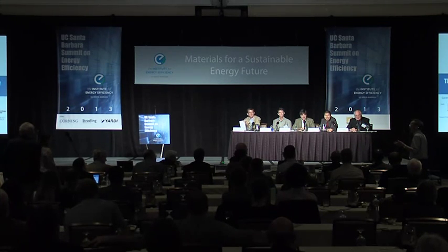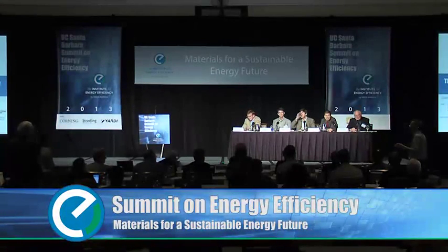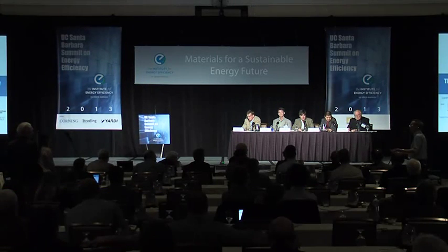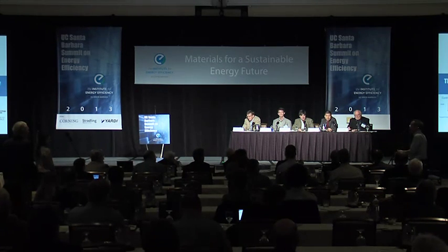First, in answer to George Crabtree's question, there is actually a need that the utility people say when I talk to them: they would like modular batteries, 50 to 100 kilowatt modules at the end of the distribution line. You can get a 1 or 2% gain in efficiency of the distribution to just do minor load leveling at the ends of the distribution line. They would like it standard size so they can move 1 module, 2 modules, 3 modules into that.